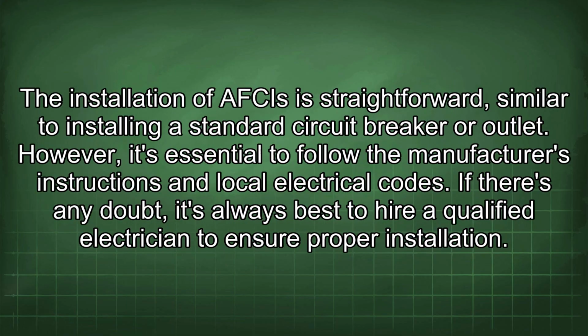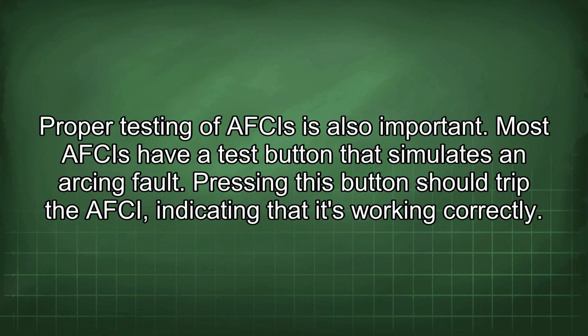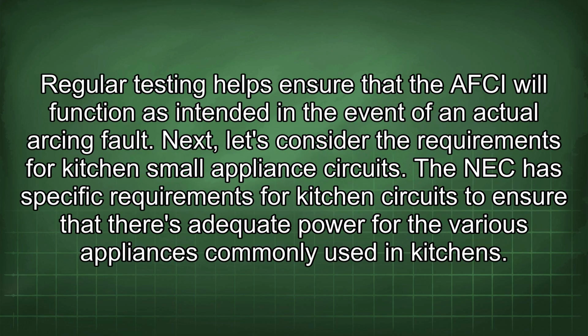The installation of an AFCI is straightforward, similar to installing a standard circuit breaker or outlet. However, it's essential to follow the manufacturer's instructions and local electrical codes. If there's any doubt, it's always best to hire a qualified electrician to ensure proper installation. Proper testing of AFCIs is also important. Most AFCIs have a test button that simulates an arcing fault. Pressing this button should trip the AFCI, indicating that it's working correctly. Regular testing helps ensure that the AFCI will function as intended in the event of an actual arcing fault.